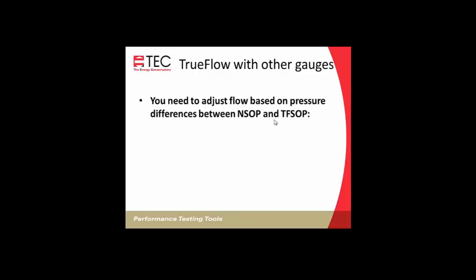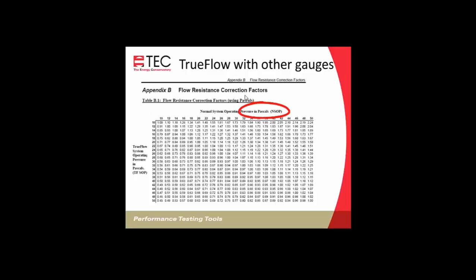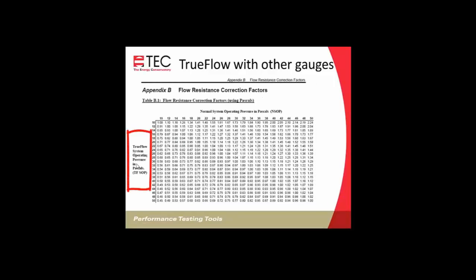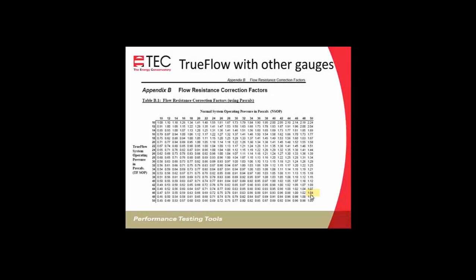Next, we'll need to adjust the flow based on the difference between the normal system operating pressure and TrueFlow system operating pressure. So we'll record the normal system pressure, we'll record the TrueFlow system pressure. We use a chart to determine the multiplier. So this is the Pascal chart. So let's say to start with, our normal system operating pressure is 50 pascals. We'll follow that down to what our TrueFlow system operating pressure is in Pascal. So let's say it's 46. That was our TrueFlow. We'll follow that across to 50 with our normal system operating pressure, and we'll see we're at 1.04.